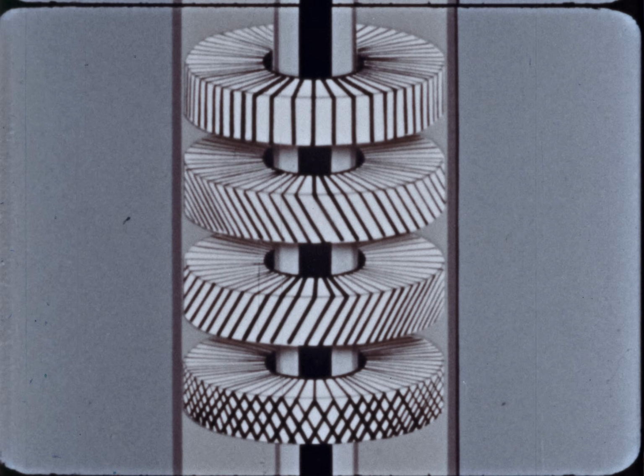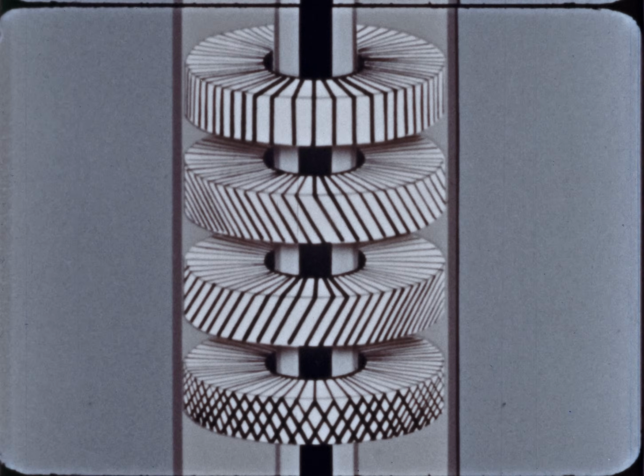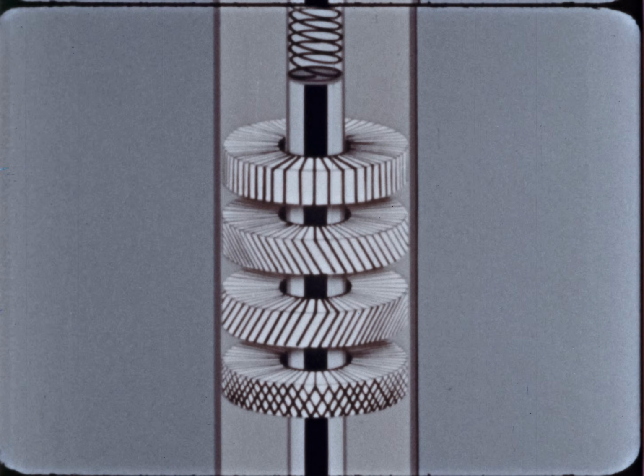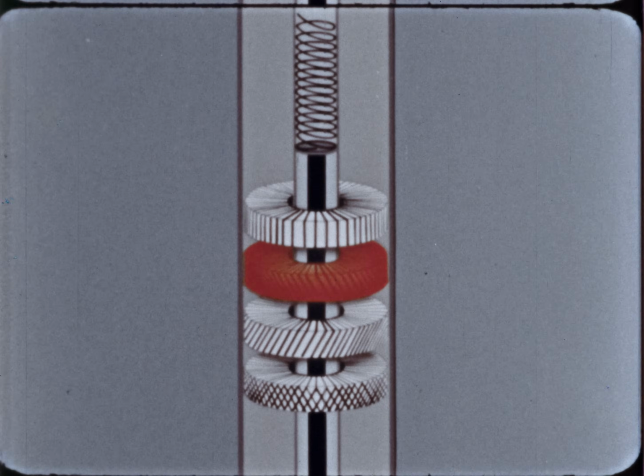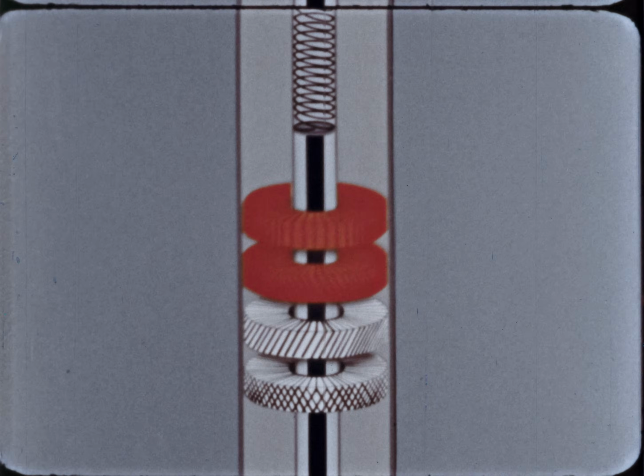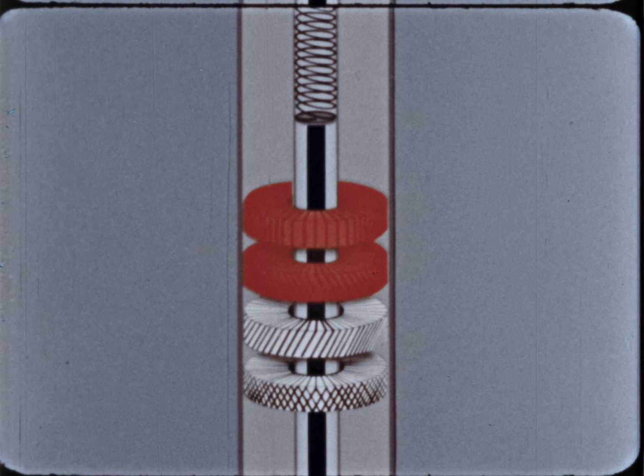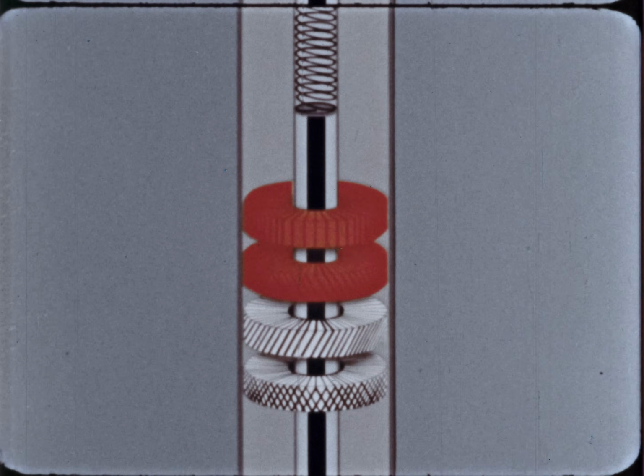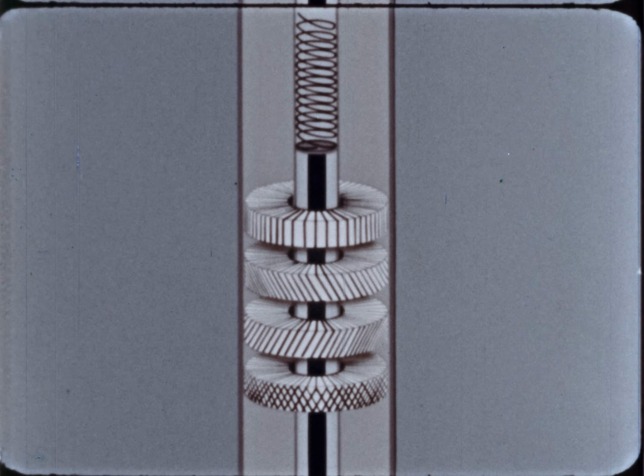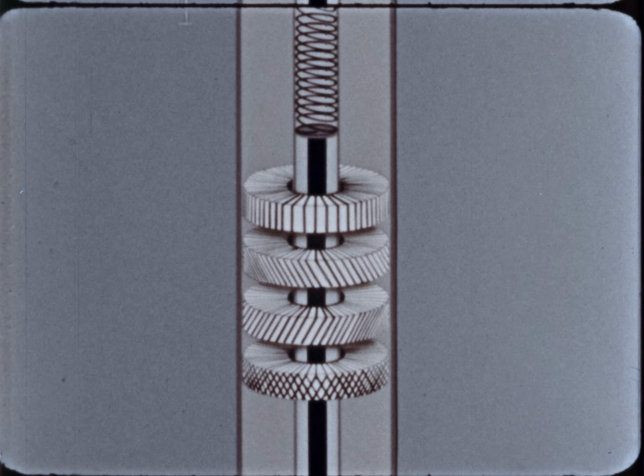The rod movement is controlled by magnetic jacks. When coils in these jacks are energized, they hold or move the rods. When energized sequentially, they move the rods by increments. Gravity and springs in the top of the rod housing will drop the rods if the current is cut. Loss of current scrams the reactor, a fail-safe feature.